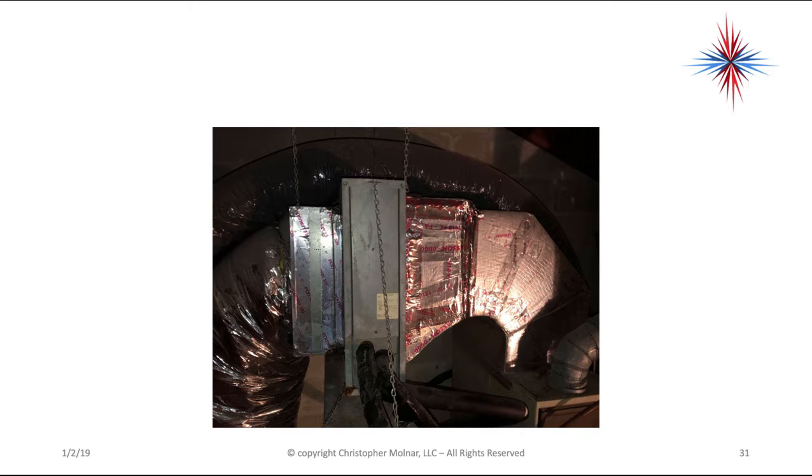Now, when we look at this picture right here, this is the coil. My furnace is over here. Okay, I'm coming up out of the furnace. I'm expanding my ductwork to come through the coil. What do you see on the other side? So right here, whoever did the right side of this did a nice job of a transition into a coil. While the top's a little rough, we're still having a nice transition into a coil.